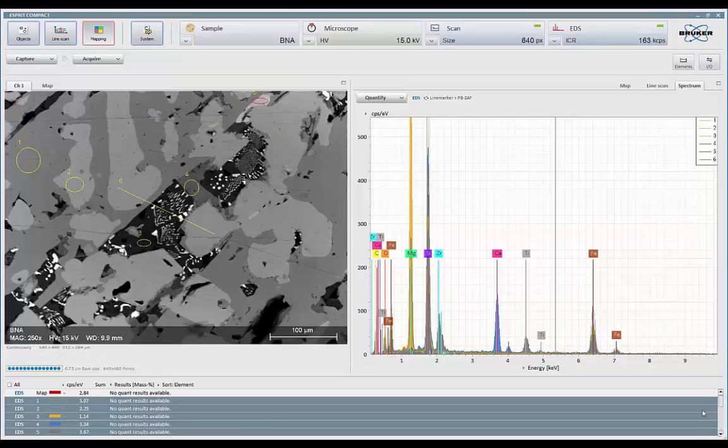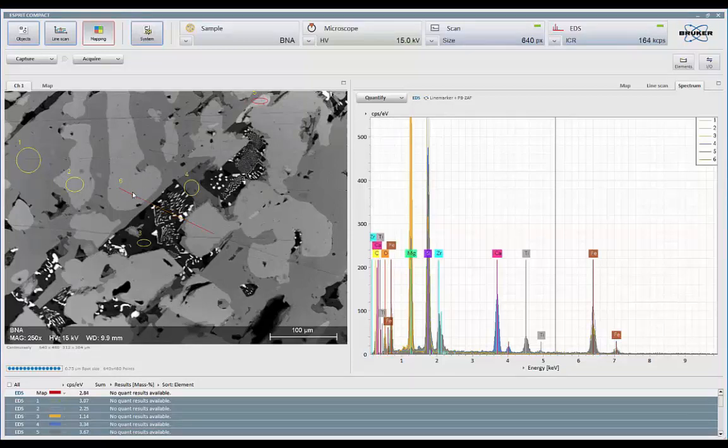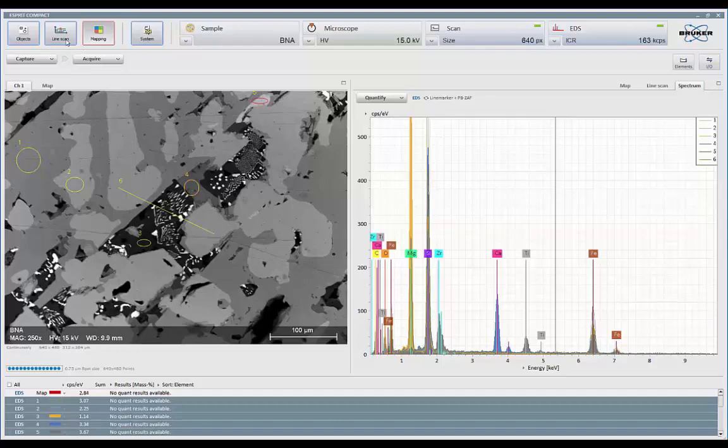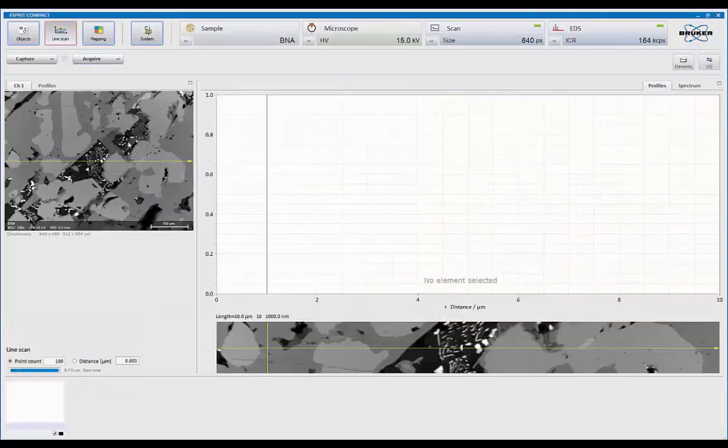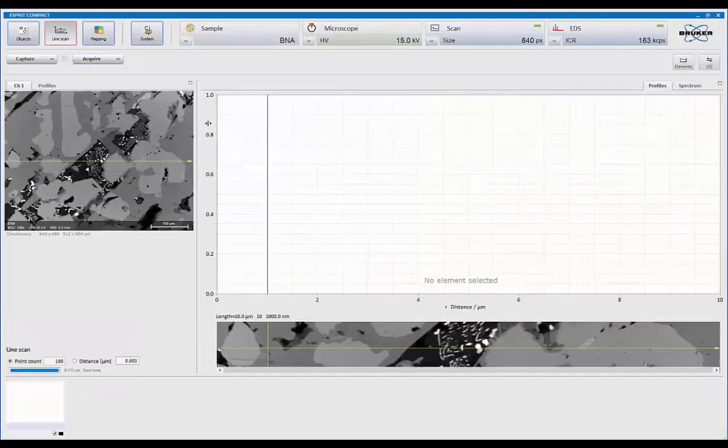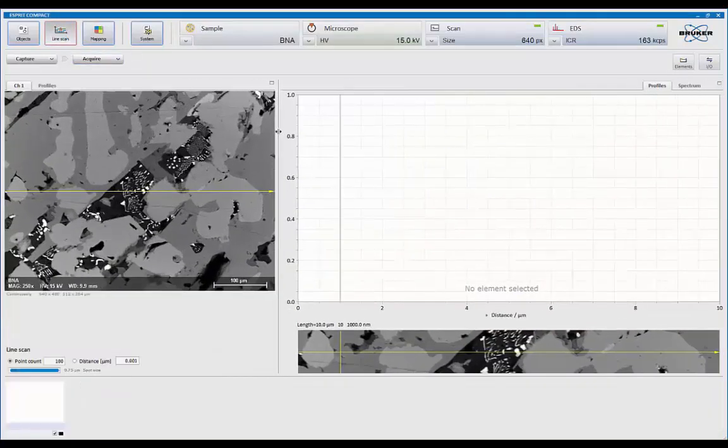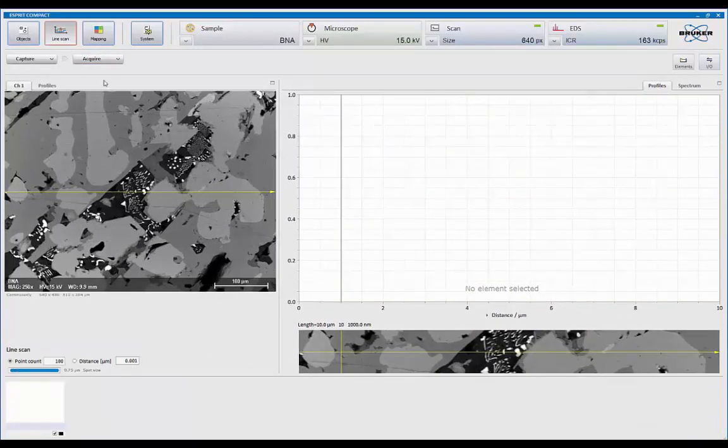Another popular analytical tool is to do digital line scans. Digital line scans many times have an advantage over maps because what it allows us to do is look at the change directly of the element along a vector. So going into line scans now, again, you can set the size of the image you want. So let's update our acquisition. So I'm going to simply go to capture.